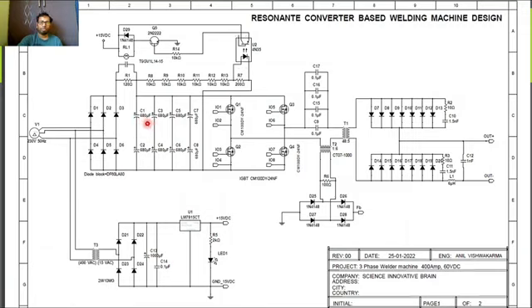If you take the whole capacitor bank, the maximum voltage is 450 plus 450, added together, becoming 900 volt DC. So we can charge this capacitor bank up to 900 volt rated, but we are actually charging it to approximately 565 volt DC with the help of this three-phase supply.